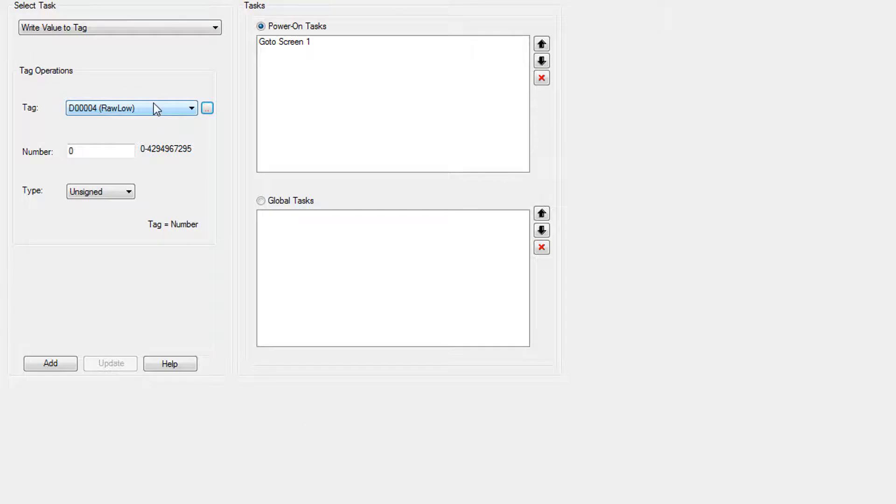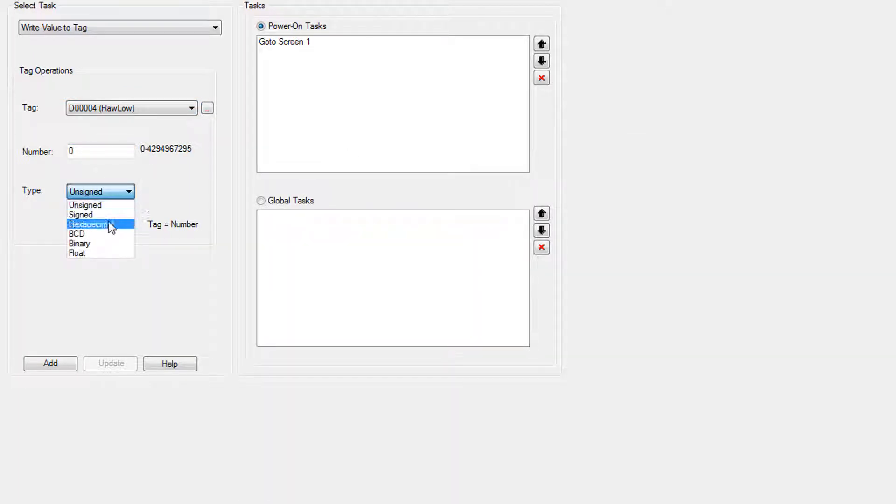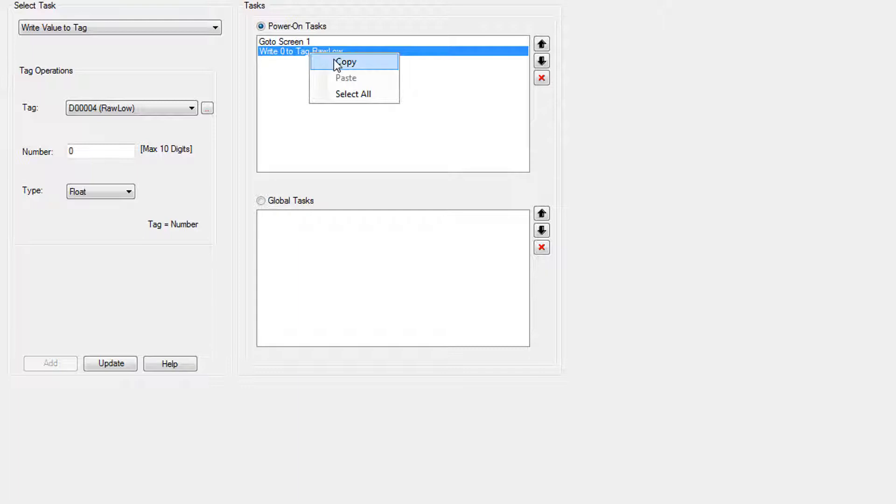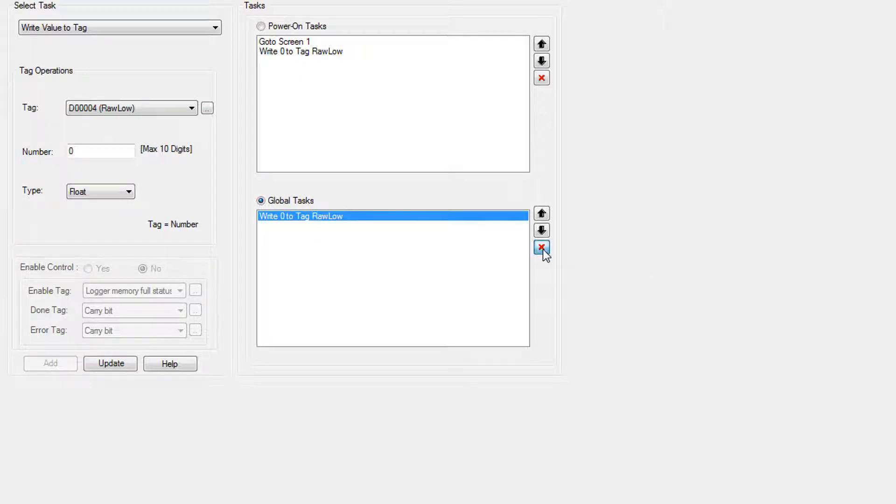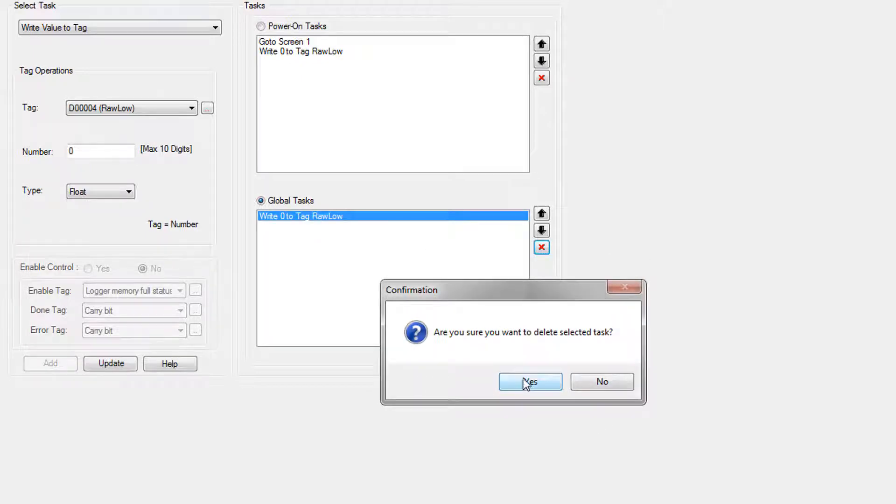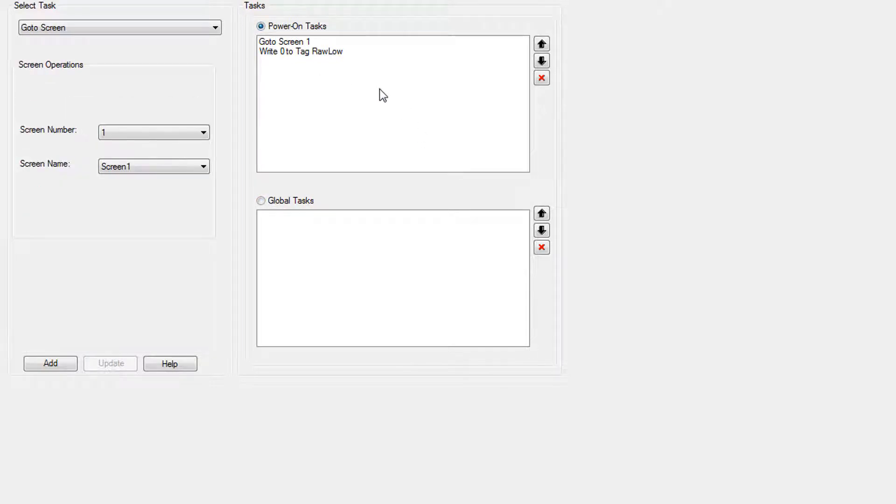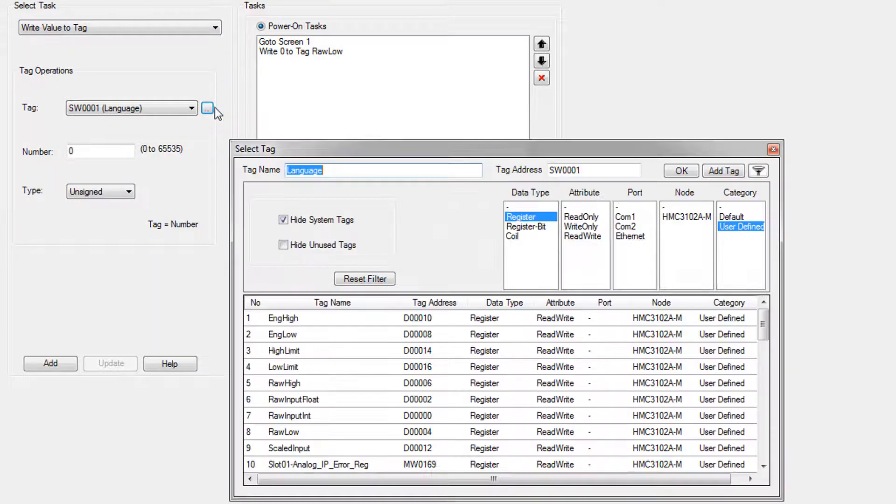But anyways, we've got rawLow as selected here. You can double click it to selected or click OK. And we're going to select float as the data type and click add. And so it's been added to the poweron tasks, write zero to tag rawLow. You can copy it. And if you really wanted to, you could paste it over here. And we don't actually want this to be continually written. So we're just going to delete it. And go back over here and select poweron task again because we're not actually done with our poweron tasks and let's make another one, write value to tag.